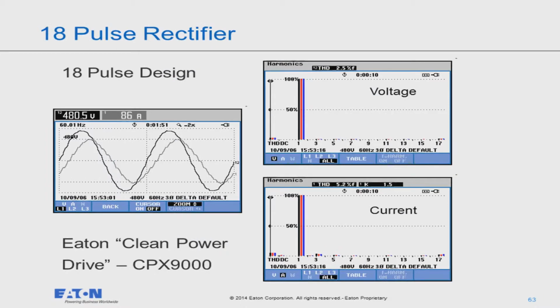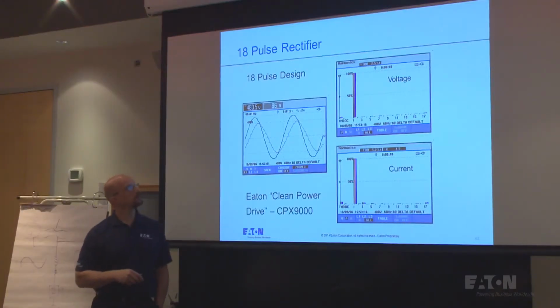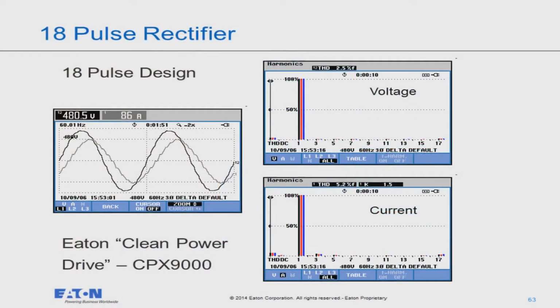Here's an 18 pulse, or what we call CPX, or clean power drive. Okay. So again, 18 pulse, we're going to typically have 17th and 19th, and those are your predominant harmonics. And so the waveform looks very, very clean all the way up through. Where do we start talking about 18 pulse drives, or typically 150 horsepower and bigger drives? Smaller drives, it's usually more cost effective to do something else. This probably less than 50 horsepower, and somewhere in that range between 50 and 150, you start thinking about where's the cost benefit of going to an 18 pulse drive.